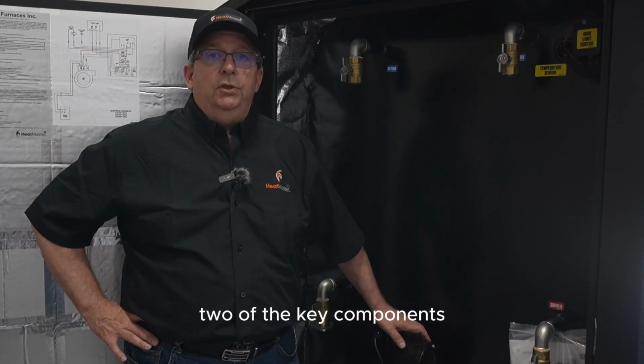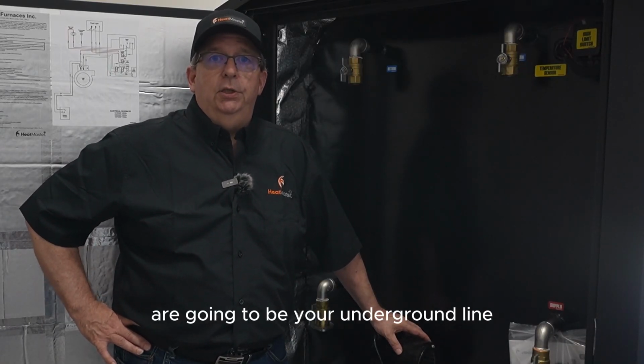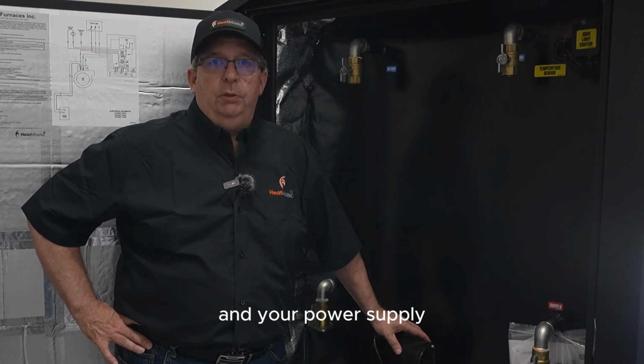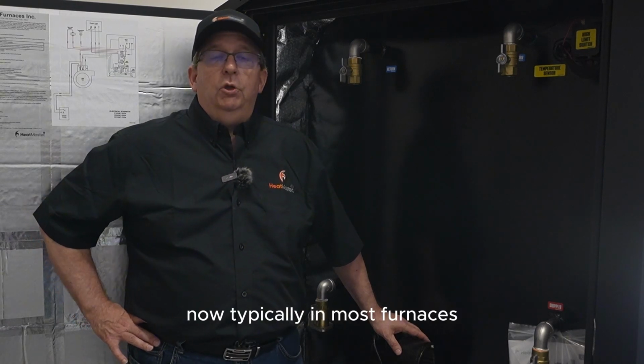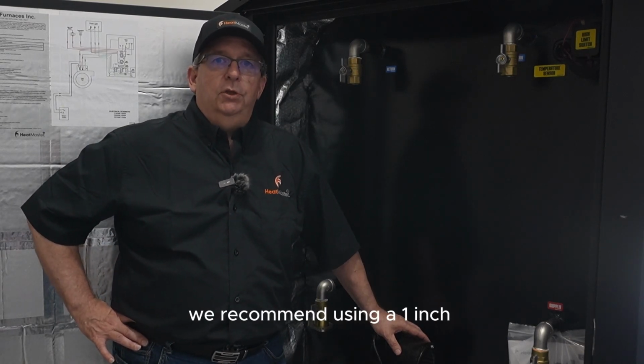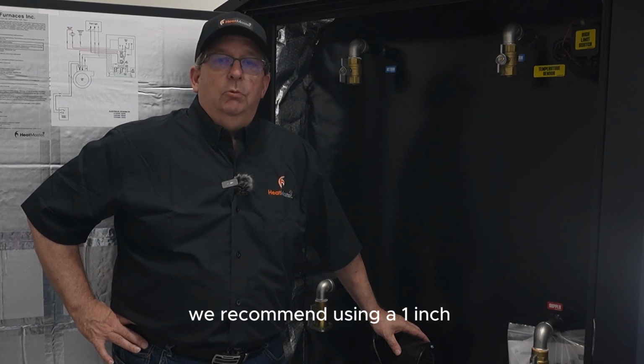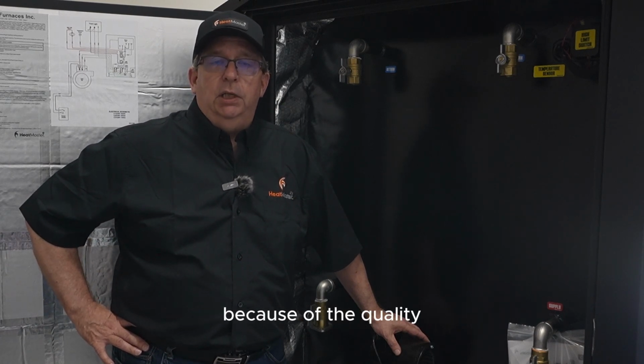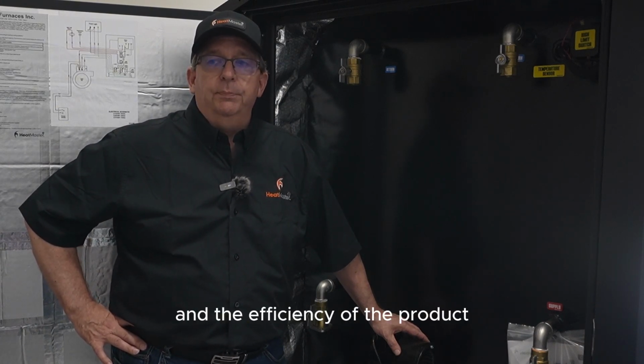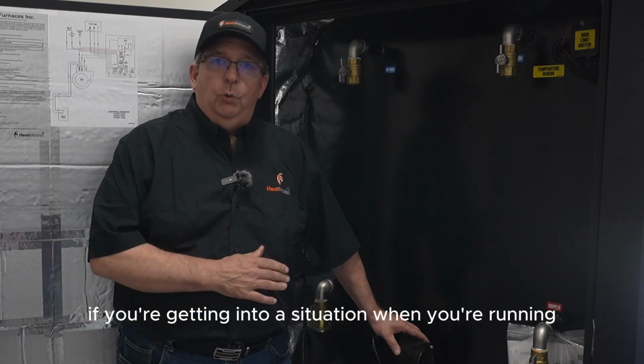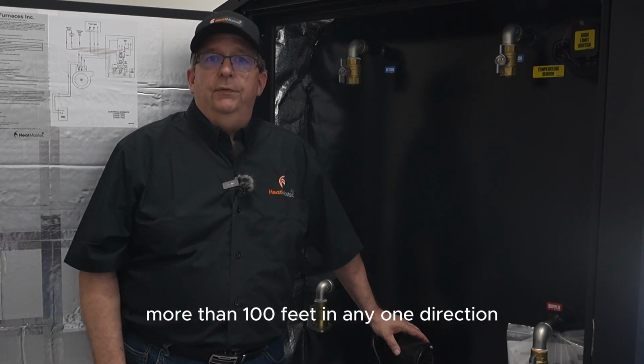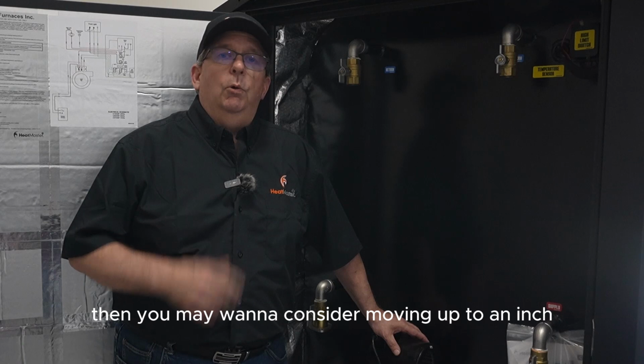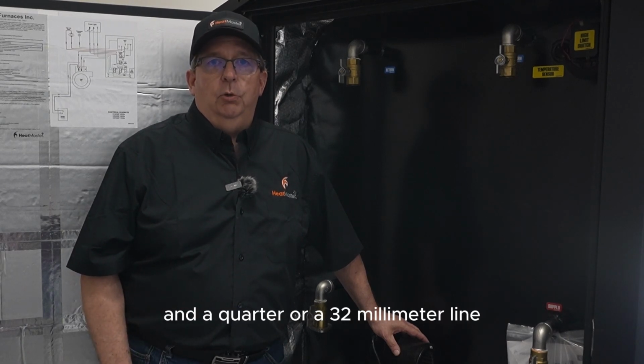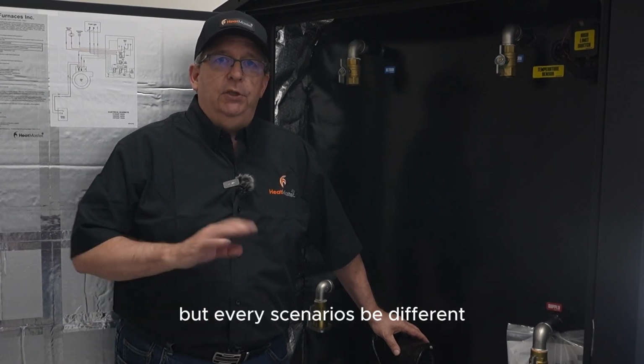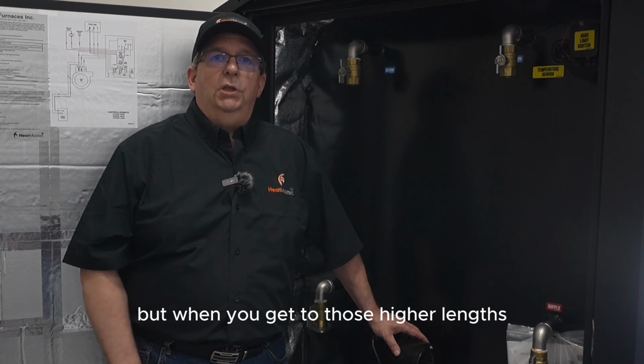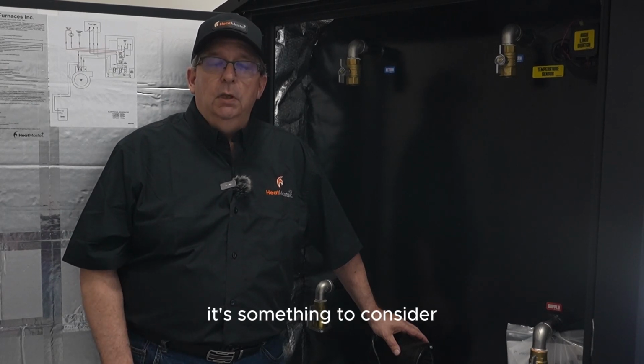Two of the key components when you're doing your installation are going to be your underground line and your power supply. Now, typically in most furnaces, we recommend using a 1-inch Rhino-Flex underground line because of the quality and the efficiency of the product. Now, if you're getting into a situation when you're running more than 100 feet in any one direction, then you may want to consider moving up to 1 1/4 inch or a 32 millimeter line. But every scenario will be different, but when you get to those higher lengths, it's something to consider.